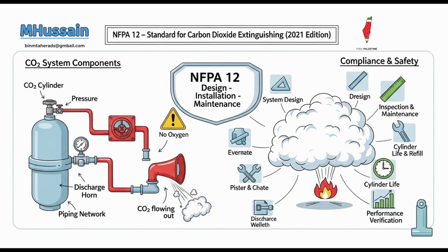Its primary mechanism of action is incredibly effective. It extinguishes fire by rapidly reducing the oxygen concentration, the vapor phase of the fuel, or both. Smothering it. To the point where sustained combustion simply cannot occur. When liquid CO2 is discharged under pressure, a large portion of it instantly flashes into vapor. Flashes to vapor. And a significant part converts into finely divided dry ice, a sort of snow, at an astonishingly cold -109.3 degrees Fahrenheit. That's minus 79 Celsius. Wow, that's freezing. Dry ice snow. Exactly. This rapid expansion and extreme cooling also cause water vapor from the entrained air to condense, which creates that characteristic white cloud you might have seen in videos. Right, the big white cloud. Yeah. So it's essentially suffocating the fire by stripping away its oxygen and also providing a significant cooling effect. Precisely.